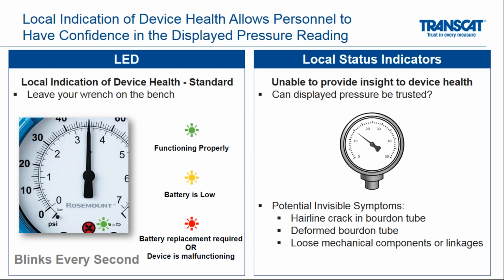But either way, it's a way that you know and the device knows that it's malfunctioning without relying on the needle to tell you that. And this would blink every second. With a Bourdon tube, there really isn't any sort of local status indicator outside of the needle. But as I've mentioned throughout this webinar, the needle is not always the best way to tell the device health. The needle might have an output, but if something has happened internally, the needle may not actually be showing the actual pressure that the gauge is supposed to be showing. Ultimately meaning that if something goes wrong, you don't have any sort of indication.